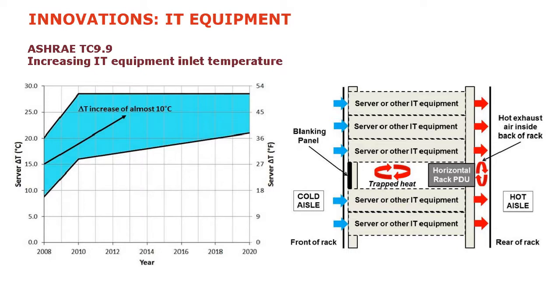So again, what ASHRAE does and why this is important is it defines the various envelopes at which the IT equipment is going to be happy. As you'll see, those envelopes expand through A1 to 2 to 3 to 4, increasingly wide envelopes of both temperature and humidity that IT equipment manufacturers will warrant their equipment within. Therefore we can operate our data centers in wider temperature and humidity ranges, which typically results in less energy consumption on the cooling side. So that's why ASHRAE is important, even though it's an American standard.